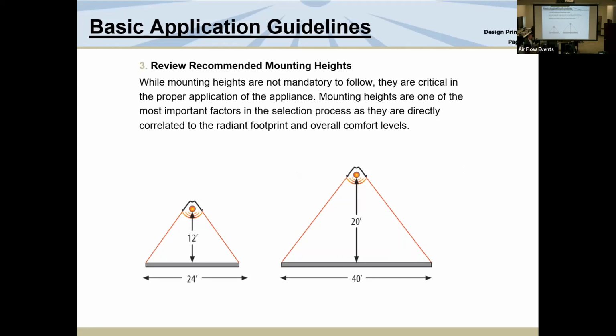It's when they put too little heat up too high or too much heat down too low that we have a problem. And as a rule of thumb, if the heater is 12 foot off the floor, that's going to give you a spread of 24 feet left and right. Okay, double. If we're 20 foot off the floor, we're 40 foot left and right.